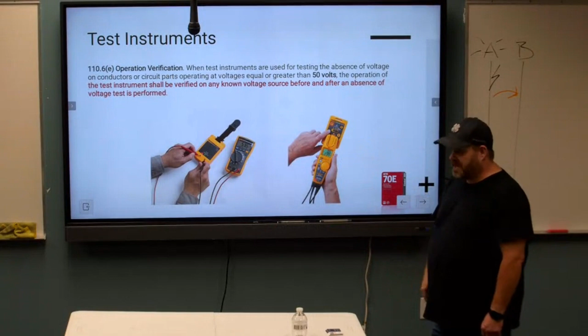We did a qualified person training and had a guy bring his own meter in—one of those Klein meters from a Black Friday sale at Lowe's or wherever. He took the cover off, looked at the back, and it didn't have a UL stamp, didn't have a TUV, didn't have any testing facilities on there. That means that meter hasn't been tested by a laboratory to make sure it'll protect you if there's a voltage spike or transient voltage in that fraction of a second.